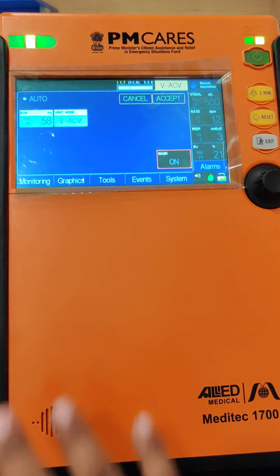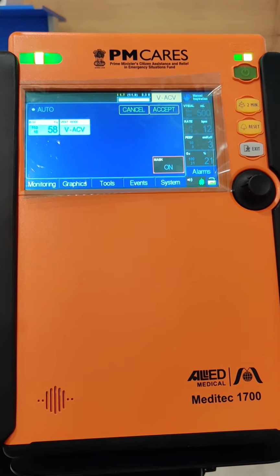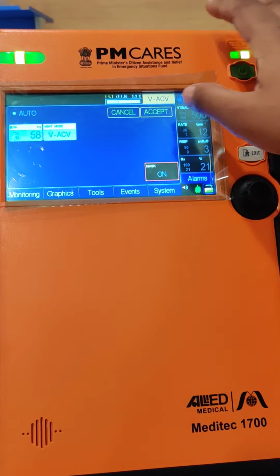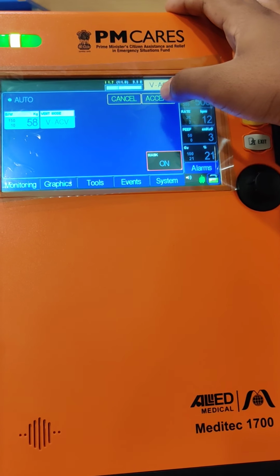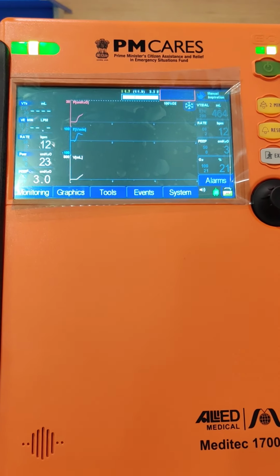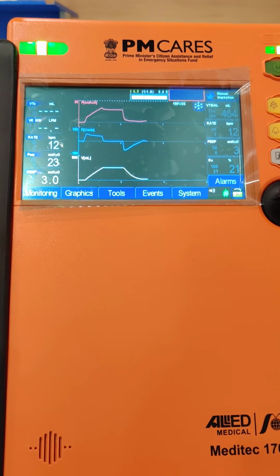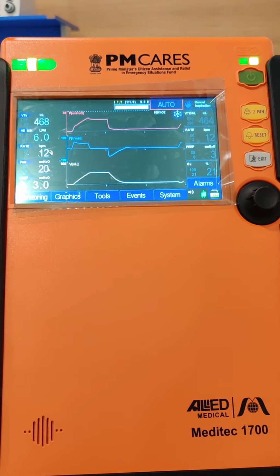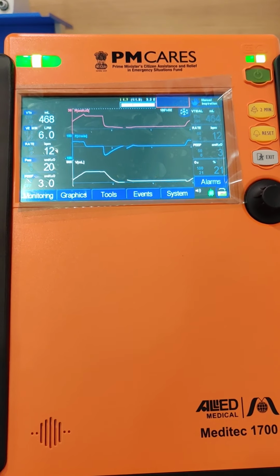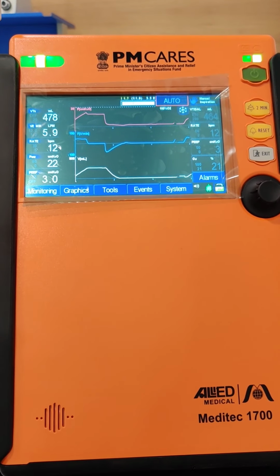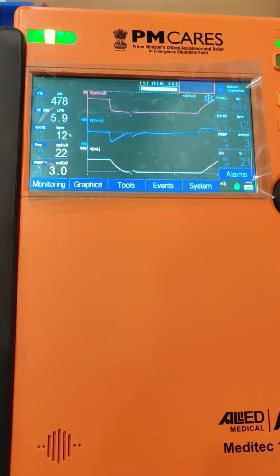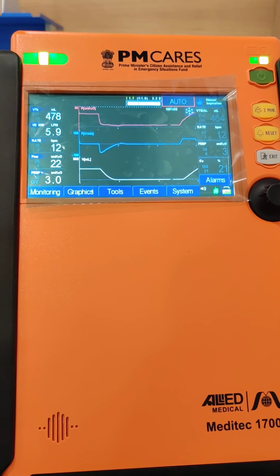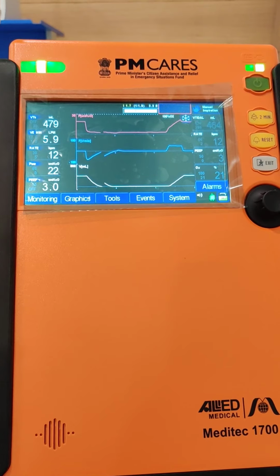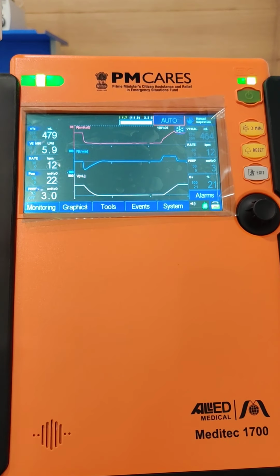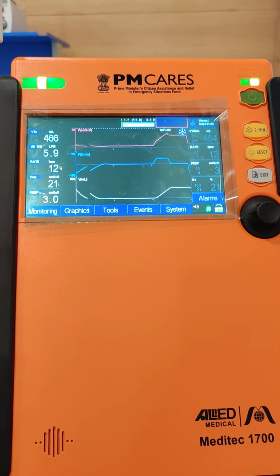So based on the body weight, the ventilator will automatically take all the readings, and it will start ventilating the patient based on this 58 kg body weight and the volume assist control ventilation. So now, depending on 58 kgs, the ventilator has started giving ventilation to the patient without doing any of the settings. So this is the auto mode, where you can set only the body weight, and the volume control or pressure control, whatever has to be delivered to the patient, and the ventilation will start automatically and in a very quick manner.